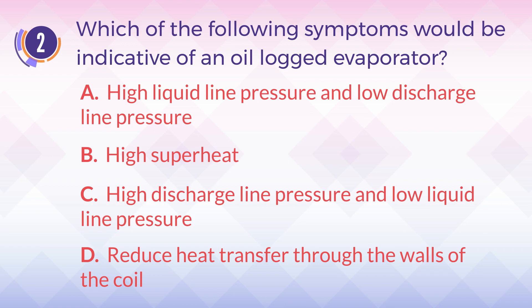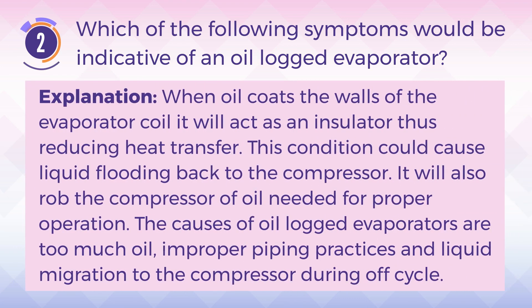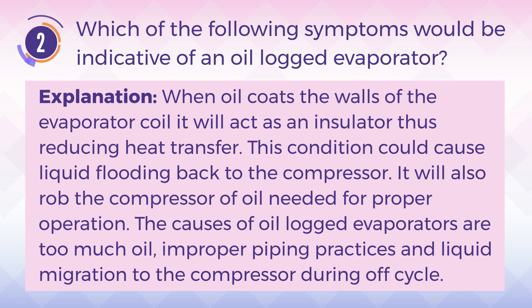The answer is D. Reduced heat transfer through the walls of the coil. Explanation: When oil coats the walls of the evaporator coil, it will act as an insulator, thus reducing heat transfer. This condition could cause liquid flooding back to the compressor and will also rob the compressor of oil needed for proper operation. The causes of oil-logged evaporators are too much oil, improper piping practices, and liquid migration to the compressor during off-cycle.